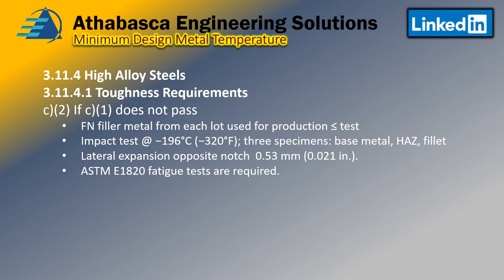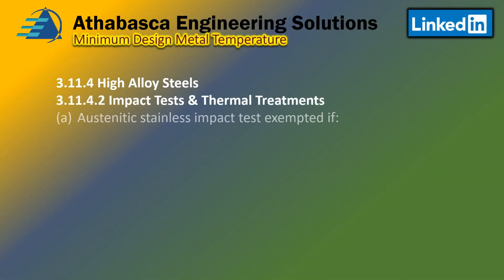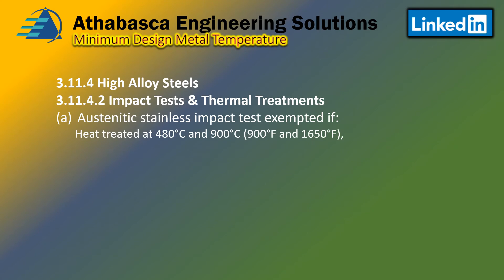The testing standard to use is ASTM E1820. Continuing with C3: if the lateral expansion for one or two specimens does not pass, then fatigue testing is required. Austenitic steels are exempt from impact testing if heat treatment is done at 480 to 900°C, which corresponds to 900 to 1650°F. The exceptions to that requirement are grades 304, 304L, 316, and 316L — they don't require that special heat treatment.